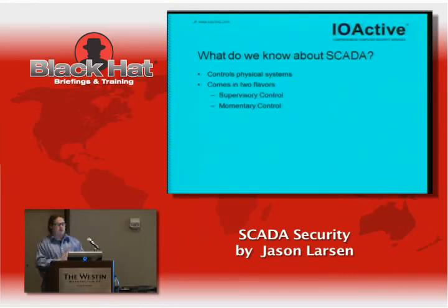SCADA systems come in two flavors, supervisory control and momentary control. Traditionally, a SCADA is supervisory control. And how we tell the difference most of the time is, if you came over there and you had a big bomb and you dropped it on top of the SCADA system, it goes poof, building's gone, everything's gone. On a SCADA system, since it's supervisory control, all the field equipment continues to work in its last programmed state until something happens that it can't deal with and it shuts down.